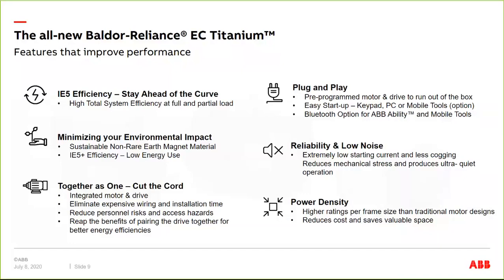Power dense, because of the high efficiency, that leads to less losses and a cooler running motor. So you'll see it here in a little bit, but we can provide in many of the horsepower sizes one frame size down than a traditional NEMA motor. And so that gives you, if you want a smaller, lighter weight motor that maybe helps with your structural design or somewhere where you're trying to fit it into a compact area. Now you pay a little cost in efficiency and it does run a little warmer, but still within a Class B rise and still within the IE5 efficiencies, which I'll show you here in a minute.